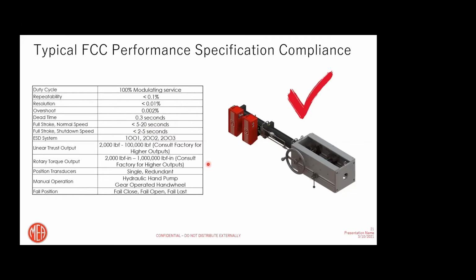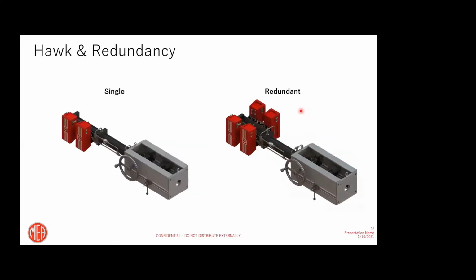Linear thrust outputs and torque outputs are easily met. Basically, all we do is change the size of the cylinder and keep everything else the same to build up more hydraulic pressure and, basically, more force. It comes with a hydraulic hand pump or hand wheel, and fail position and fail last on loss of power as a standard. And of course, the ESD module if required.